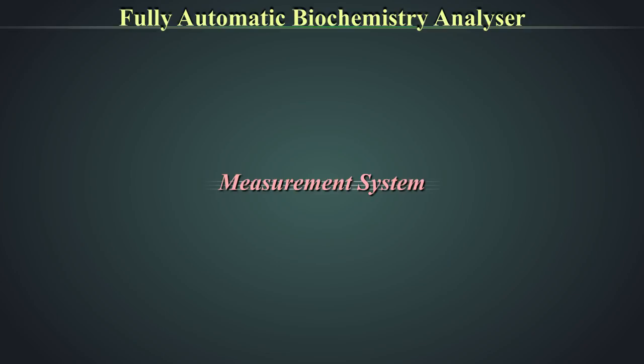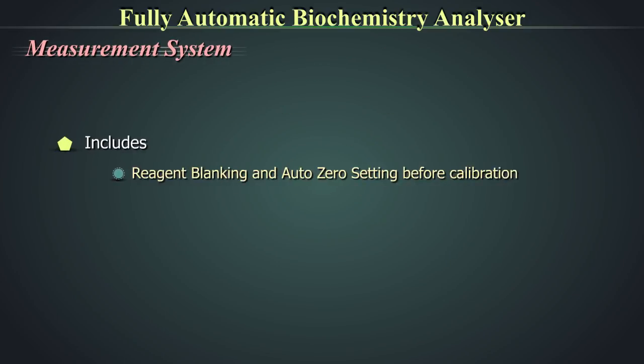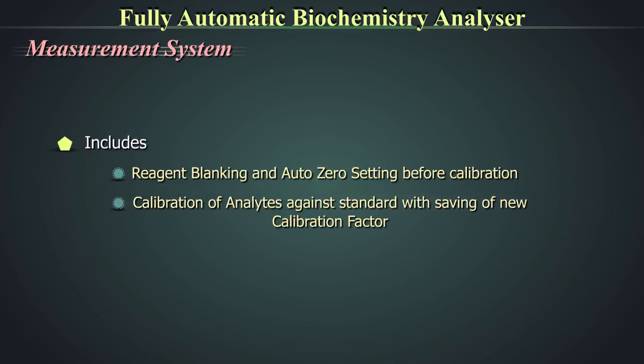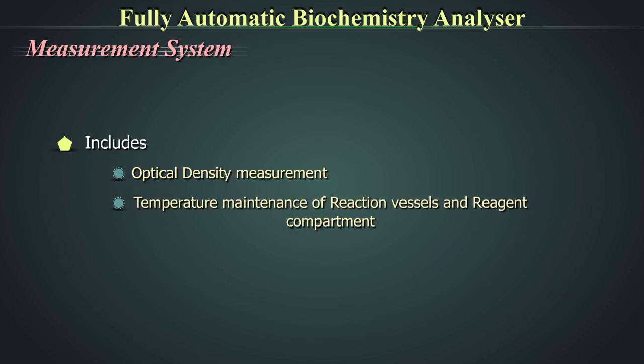The measurement system includes reagent blanking and auto-zero setting before calibration, calibration of analytes against a standard with saving of new calibration factors, optical density measurement, and temperature maintenance of reaction vessels and reagent compartment.